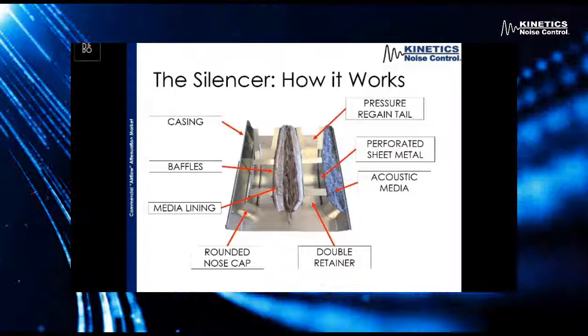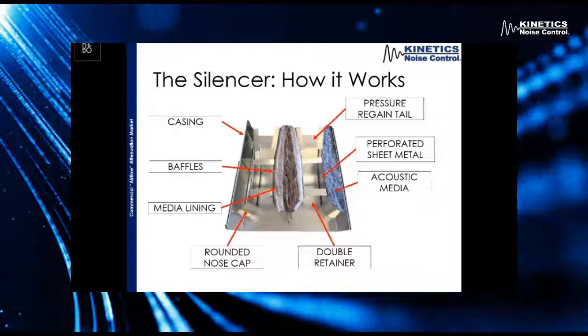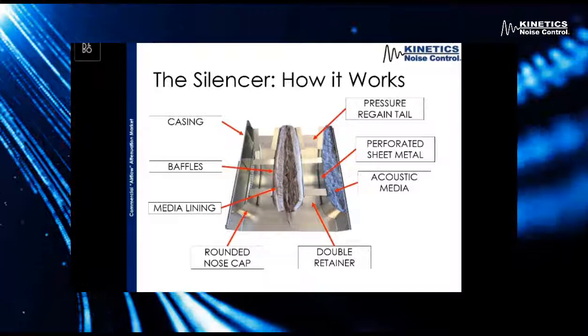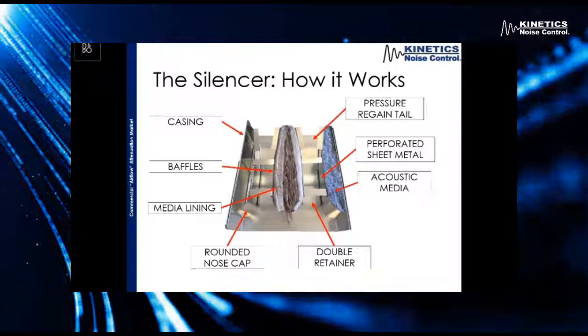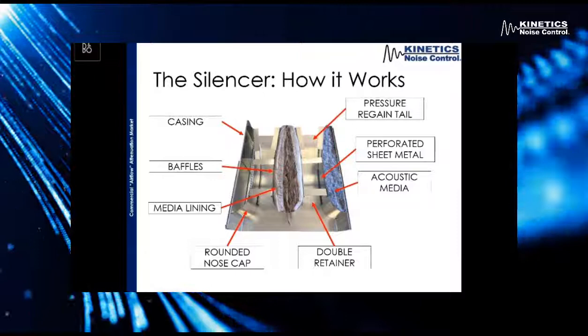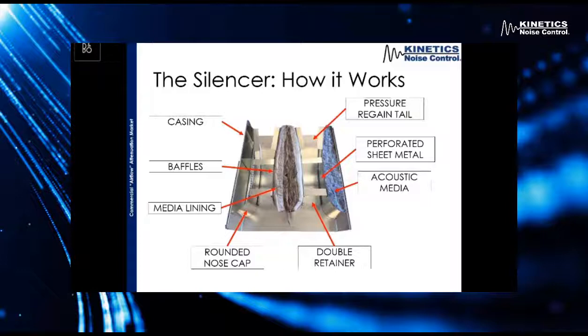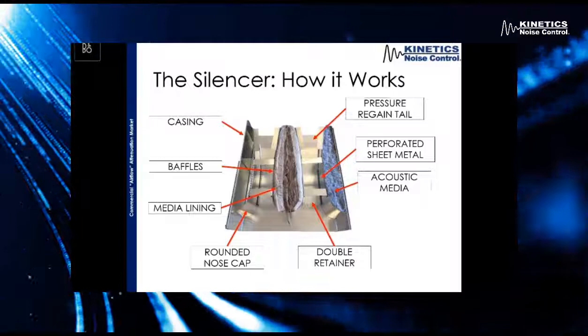This is the inside of a silencer — it looks a little funny because this is a sample, but we'll go through the main features. The first one is the outside casing, which is what holds the silencer together. We select the casing based on what the ductwork is — generally it's going to be the same gauge thickness as well as the same material. Our standard would be a 22-gauge galvanized steel casing, but we can also do 304 or 316 stainless steel, aluminum, or go to thicker gauges like 16, 12, 10, etc.